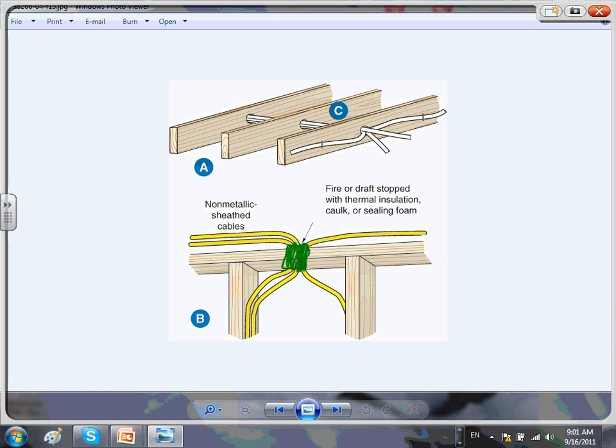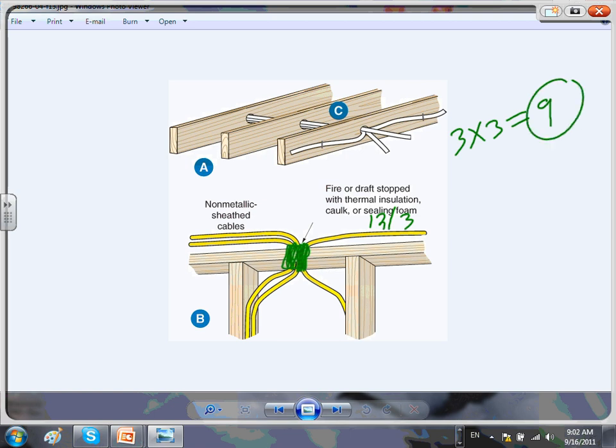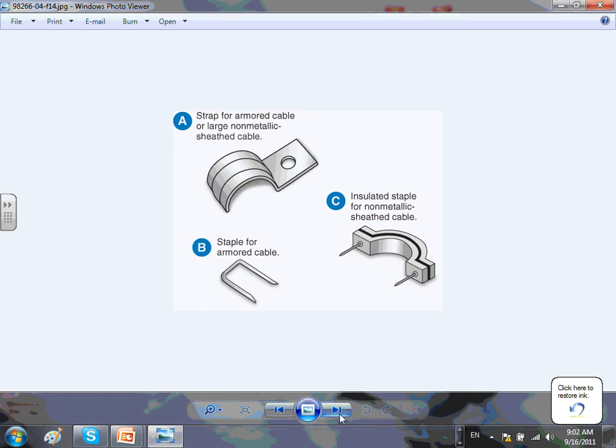For example, if this is 12/3 cable — how many conductors do I have? Three of them, all carrying current. So I have 3 times 3 equals 9 conductors carrying current. I have to derate based on 9 conductors carrying current. For number 12, after you derate, you still get your 20 amps non-continuous and 16 amps continuous. So don't sweat it too hard, but you are supposed to derate because of trapping the heat.